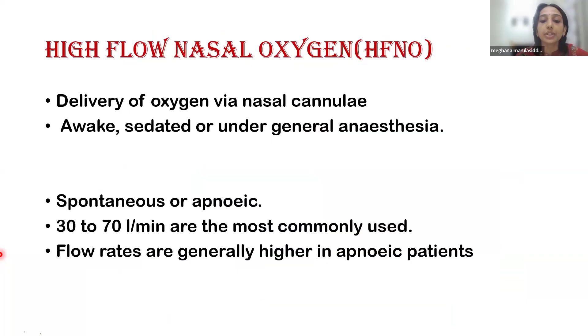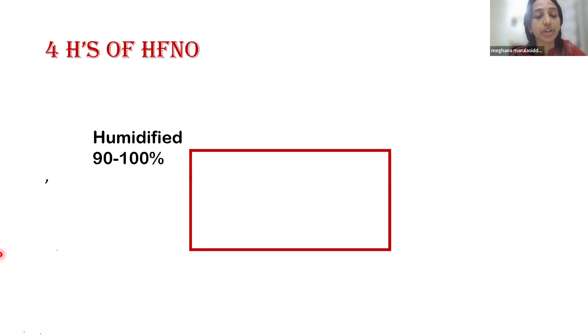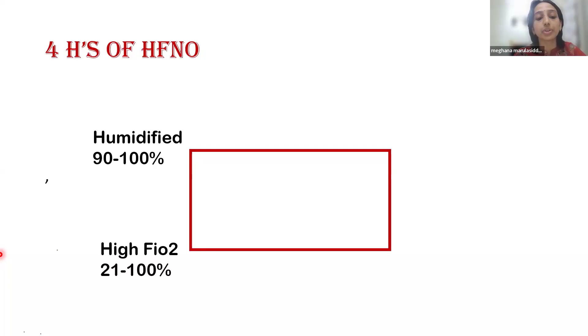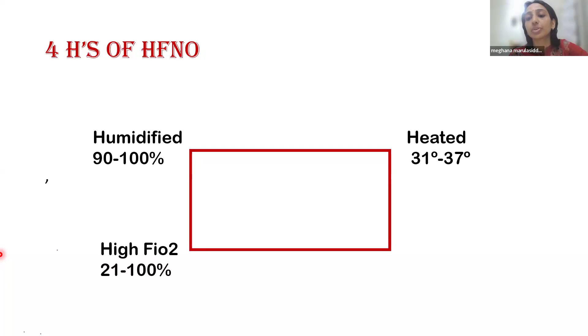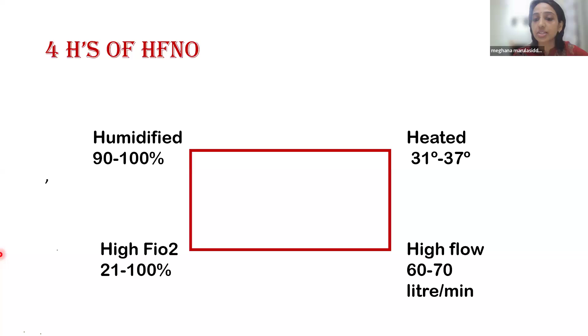Now, to understand what HFNO is, let us look at the characteristics of HFNO. HFNO consists of 4 H's, and we will see what they are. The first one is humidified: the gas provided in HFNO, whether it is 100% oxygen or an air oxygen mixture, is humidified almost up to 100%. The FiO2 provided is high, and the important thing to remember is the FiO2 is constant. We can provide an FiO2 from 21% to 100%. It is heated from 31 degrees to 37 degrees, and it is high flow in the range of 60 to 70 liters per minute. An important thing here is that these variables can be controlled independently.